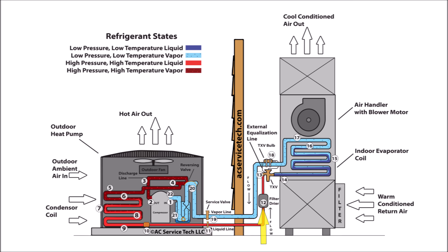In step twelve, you have the subcooled liquid entering the filter dryer. The filter dryer's job is to trap any debris and water. It has a limited capacity due to its size in order to absorb water, and the refrigerant remains in the subcooled liquid state. After the refrigerant exits the filter dryer, the high pressure, high temperature liquid refrigerant enters the metering device at step thirteen.